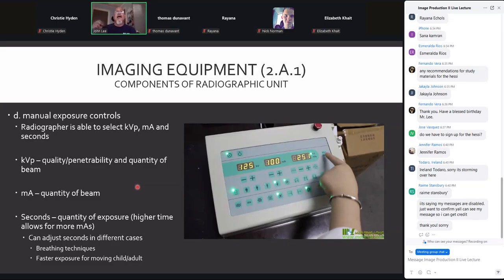Seconds determines the quantity of the exposure over the period of time of that exposure. Okay, so it also determines how long those electrons are going to be flowing from cathode to anode, thereby producing X-rays. And remember, all of our technical factors are within our purview to control and manipulate as we see fit.